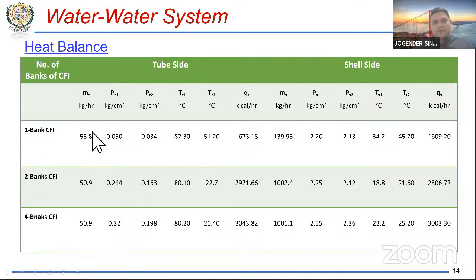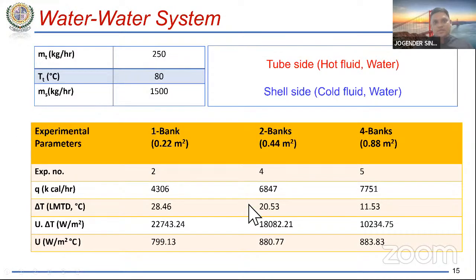So if you see this for 1 bank, 2 bank, and 4 bank: in 1 bank CFI, for a tube side flow rate of 53.8 kg per hour, the Q in the tube side is 1673.18, and the Q, that is heat flux, in the shell side is 1609.20, which is pretty much the same value. If you want to find the percentage difference, it will be very small. So we concluded that we had achieved a steady state condition and could note down the readings. We can note down the inlet temperature and outlet temperature of the fluid, and then make different calculations. Similarly, for 2 bank it is 2921 here and 2806 there, and for 4 bank 3043 here and approximately 3000 there. Both are approximately the same, so we can take the values. This heat balance is very important.